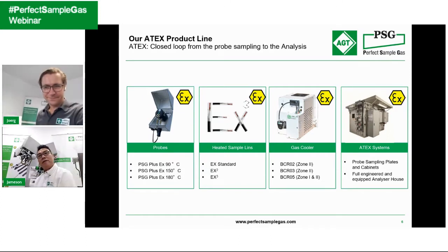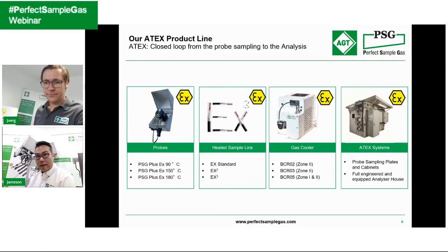The third item we have is the gas cooler — a process gas cooler, also used for emission measurement, for both positive pressure or negative pressure, in zone one as well as zone two. For positive pressure, you can use an auto drainer so that we can drain it from the bottom.